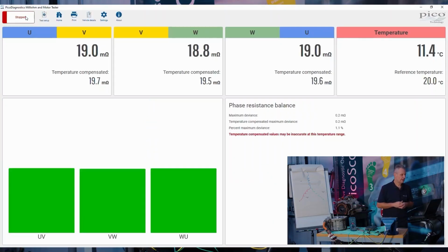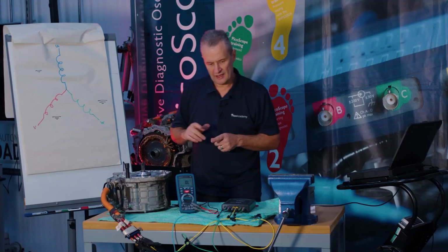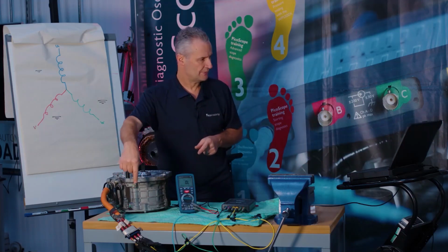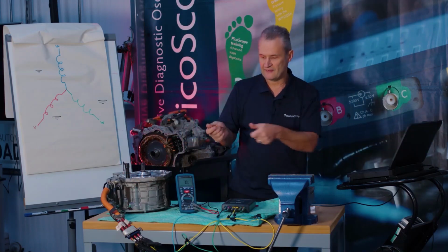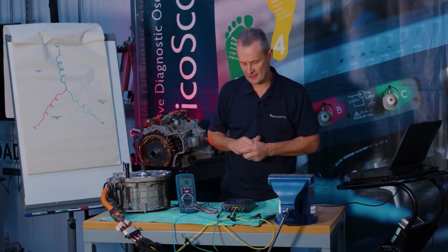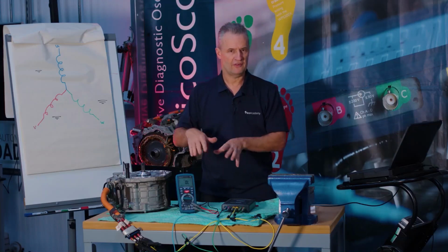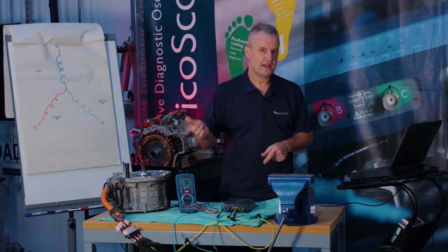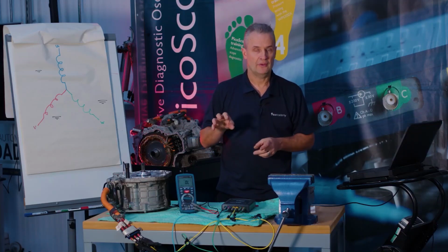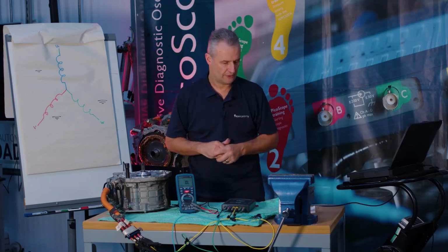19 milliohm, 18.8 and 19 milliohm. The bar graph tells us that those phases are balanced. Now, depending on specification, that is either good or bad. I believe that is okay for that motor. The balance is what's important there, but just grasp for a second how low that resistance is. 18 milliohm, 19 milliohm. It's a tiny, tiny resistance. On that subject, if ever you do get an erroneous measurement, repeat the test. Before you repeat it, take your clips off, reapply them, and repeat the test. If you then get a good result, that was obviously a connection error. If it's the same phase with the same error, then that is most probably a true erroneous reading, and then of course we have to diagnose further with the motor.